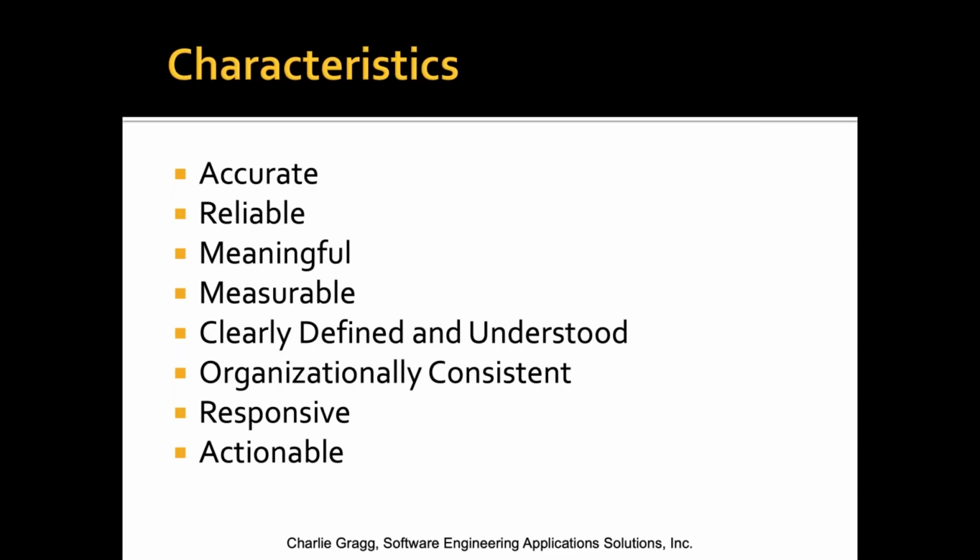With one client a few years back, I helped to improve their CAPA metrics, and I went around to the different groups within the organization. And one group considered the CAPA closed when the investigation was complete. Then they opened another CAPA for the corrective action. They closed it when the corrective action was complete and opened another CAPA for preventative action. In their management reviews, this group had many more CAPAs than other groups, but their closing times were considerably faster, which they considered a plus. Metrics need to be apples to apples and not apples to grapefruits.